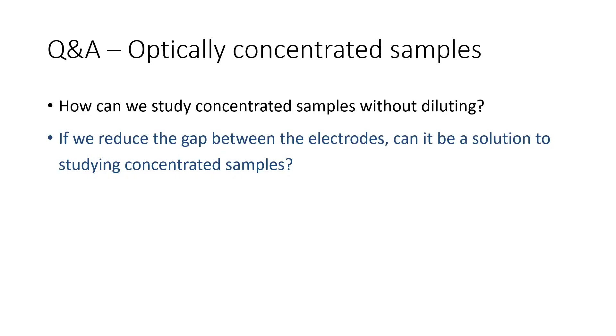If we reduce the gap between the electrodes, can it be a solution to study concentrated samples? No, but it is a solution to study high salt concentration samples and nonpolar samples. In both cases, it allows a smaller voltage to be used to generate the same electric field used with other cells, such as the folded capillary.